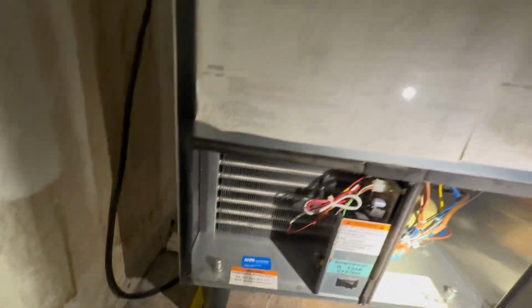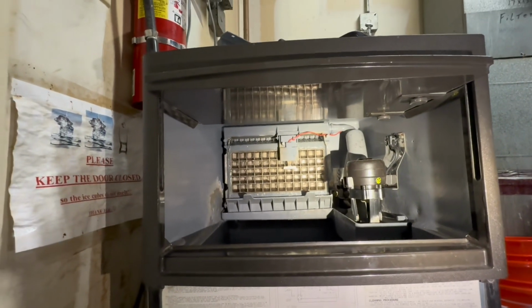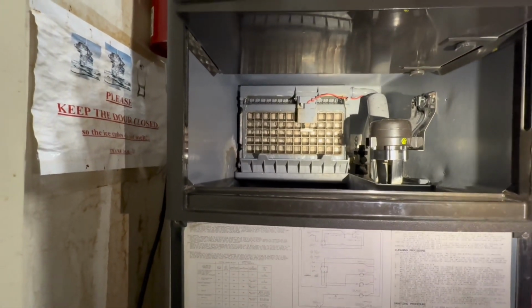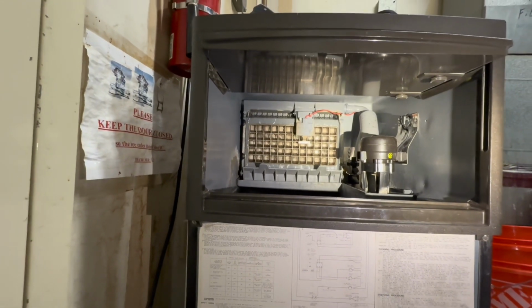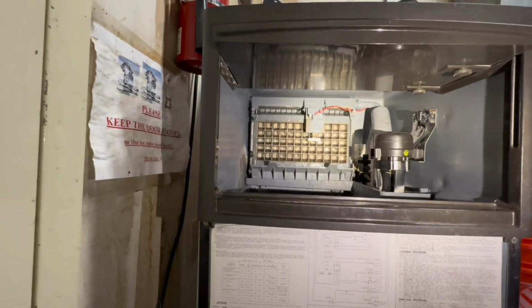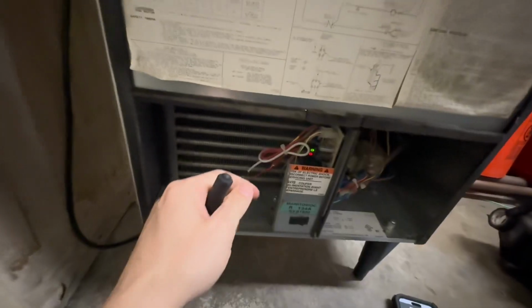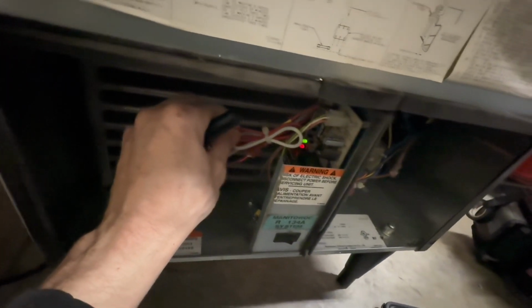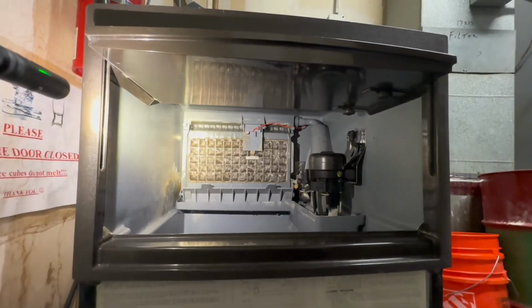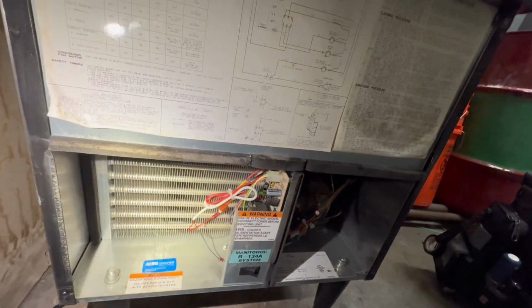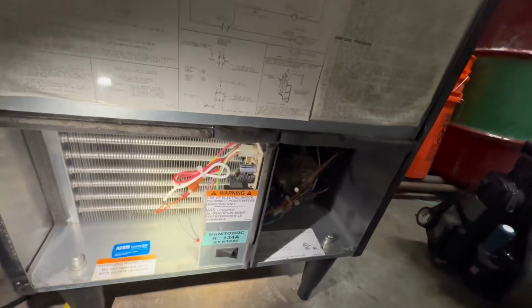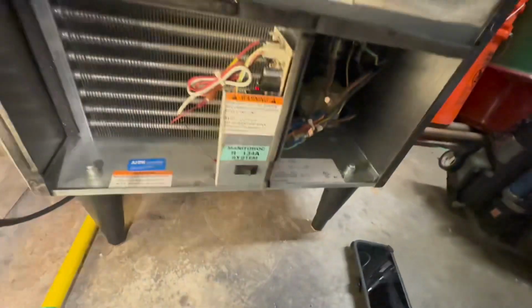Nothing sticking out as of yet as to why this machine shut off, but we're gonna at least wait for it to cycle into harvest, see if ice actually harvests, aka drops off the evaporator. If not, we will move on to the next step. So my harvest light on the control board is kind of going on and off right now. That's because we almost have a complete sheet of ice and we're getting ready to go into harvest. Once that light is on steady for, I believe it's 7 to 10 seconds, somewhere in that range, the machine will cycle into harvest and we'll see what's wrong with this machine.